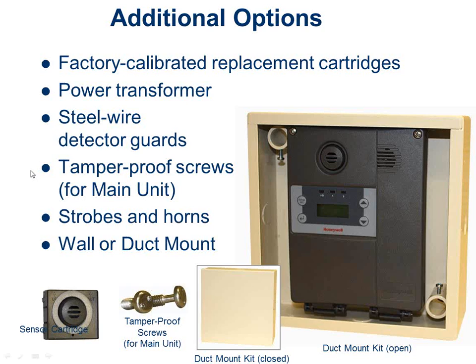In any case, that's my sidebar discussion. You can mount these on the wall, which is very typical. In HVAC applications, we sometimes mount them in ducts. Typically, we do that with an aspirator box. It's the same sensor you'd put on the wall, but we put it in a box like we're showing here on the right-hand side, right? And then we have tubes that go out into the duct and come back. So I can draw a little bit of air in from the duct and put a little bit of air back in the duct. I get a little circulative pattern happening so I can sense air inside my aspirator box.